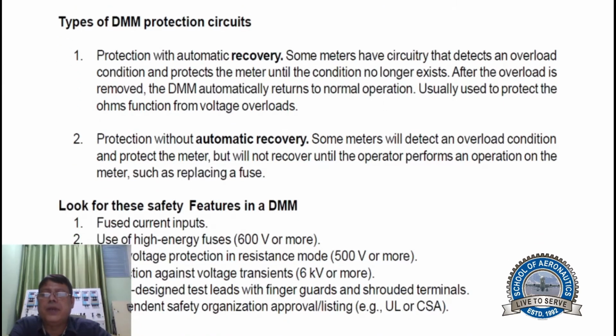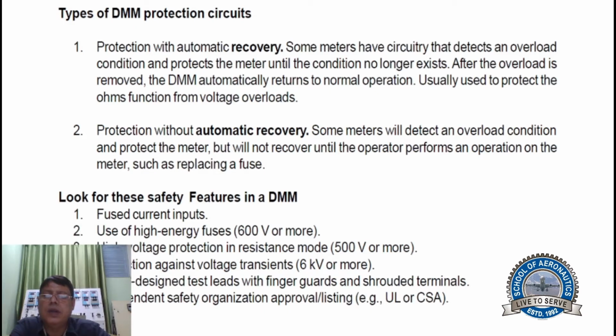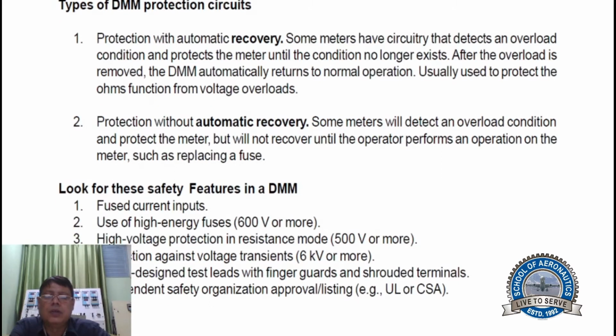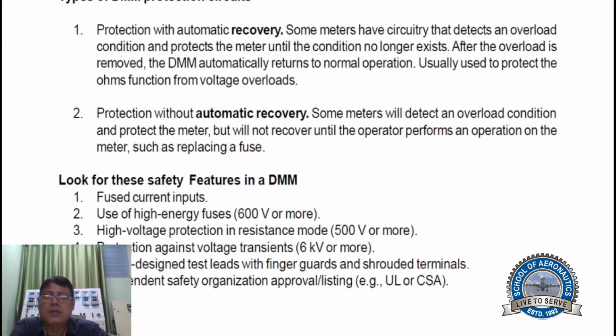Look for these safety features in a DMM. Fused current input, using high energy fuses of 600 volts or more. High voltage protection in resistance mode for 500 volts or more. Protection against voltage transients of 6 kV or more. Safety design test leads with finger guards and shrouded terminals. Independent safety organization approval listing, that is UL or CSA.